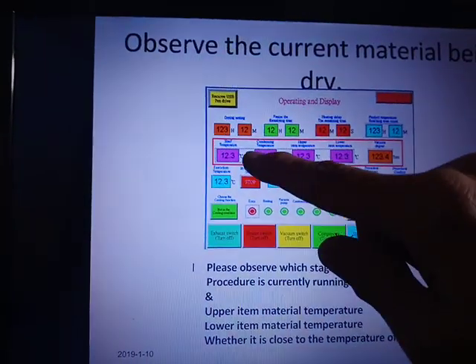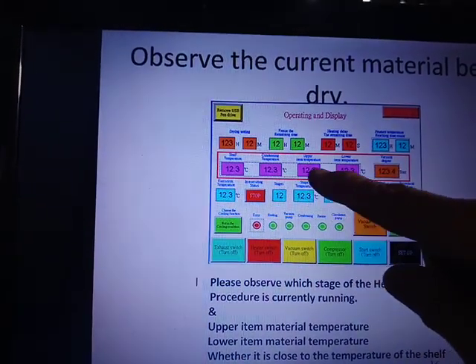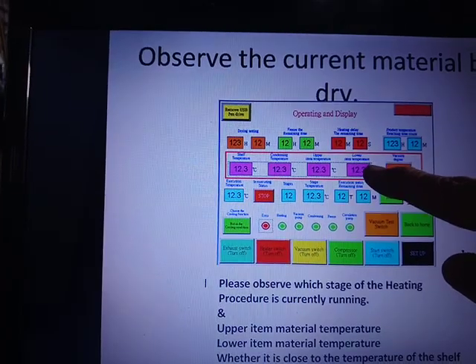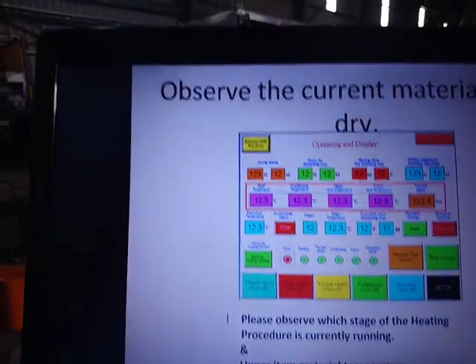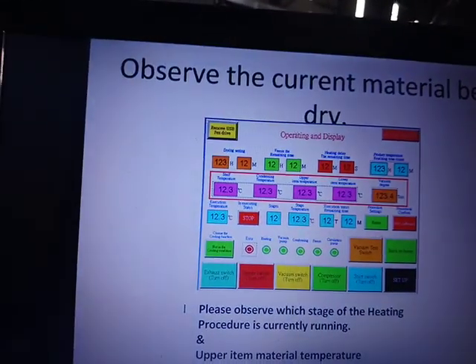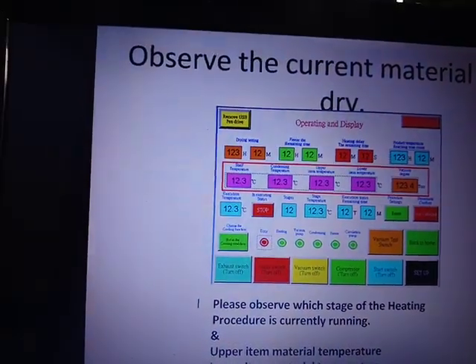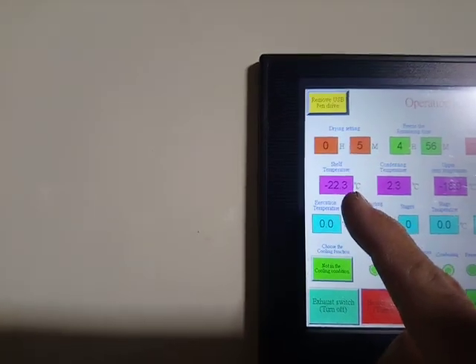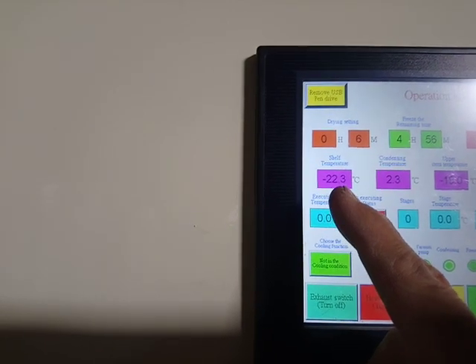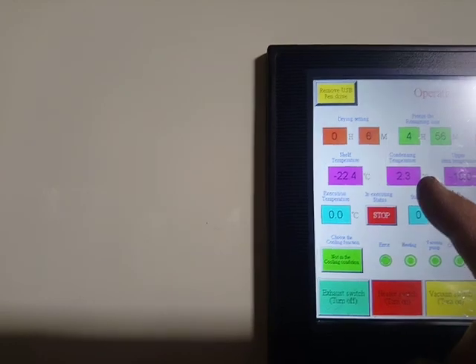At any time you can check the shelf temperature, the condensing temperature, the upper item temperature, the lower item temperature and the vacuum degree. It will help you judge whether the fine drying is finished. We mentioned the shelf temperature. Right now it is minus 22.3. This is the shelf. And the condenser temperature shows here. This is the condenser.